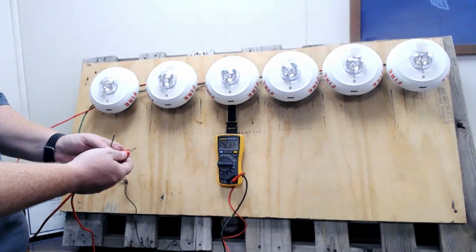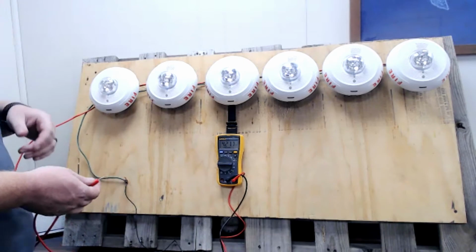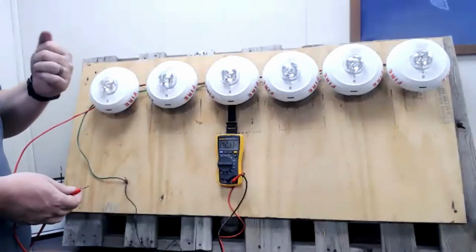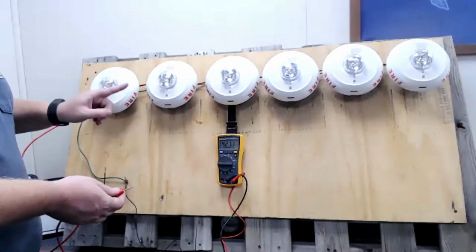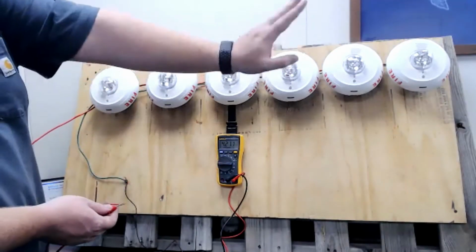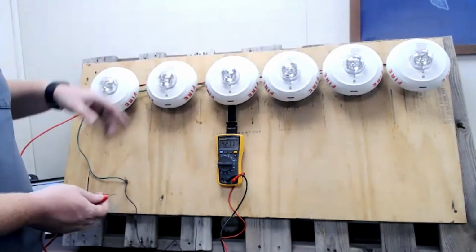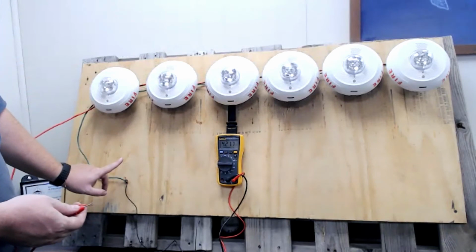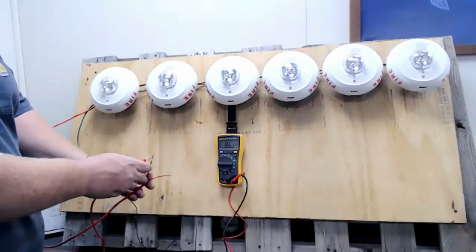So I see 4.2 K ohms. Now I should see an open circuit if I didn't have any reference to ground. But that 4.2 K ohms, if y'all remember, is the same thing we saw when we were checking for the end-of-line resistor. So it tells me that there's possibly a ground fault on the negative lead, and what's happening is it's going all the way down the red conductor, coming across the end-of-line resistor, and then coming back to wherever our ground fault is, and coming over to the earth ground that my black meter lead is connected to. So to verify that, I will touch it against that one, and I have 1.2 ohms.